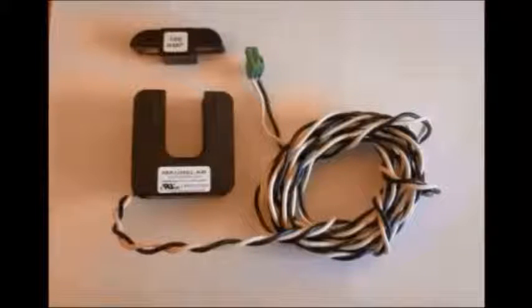The eGauge system uses split-core CTs to monitor the current flow of a given conductor or circuit. In this photo, we see a 100 amp split-core CT. This type of CT is generally used to monitor the total utility demand of a residential home. One CT on each phase of a 240 volt system.